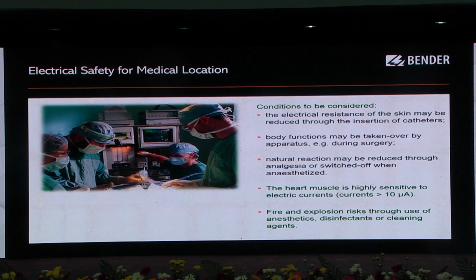Whenever a patient dies, they ask for proof. During the operation, they say it was low BP or high BP, but they ask for the standard and where exactly the low leakage current was. You have to show the equipment. That is the reason we can record the leakage current and identify it online.